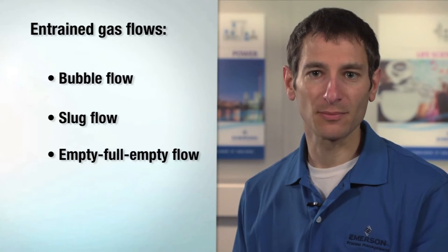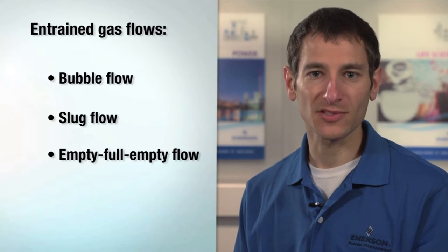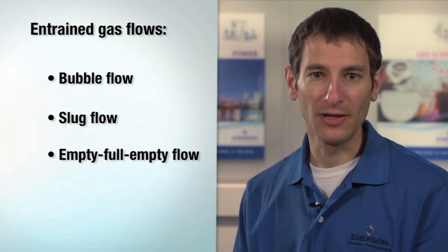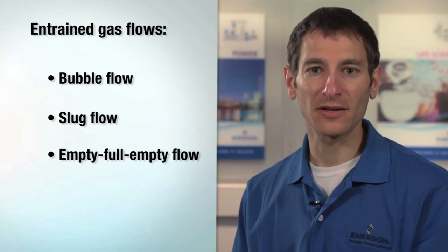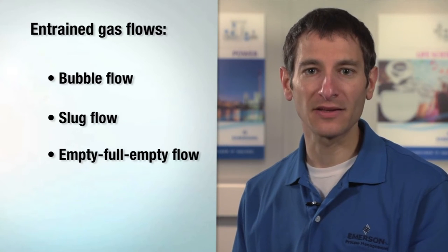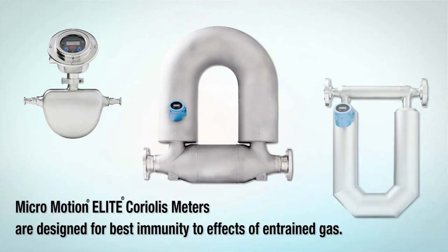We'll discuss three distinct types of entrained gas flows: bubble flow, slug flow, and empty-full-empty flow, and how they can occur both intentionally and unintentionally. Micro Motion ELITE Coriolis meters are designed for best immunity to the effects of entrained gas.